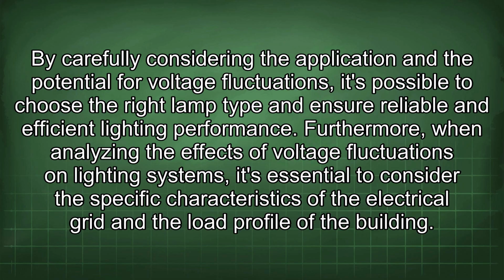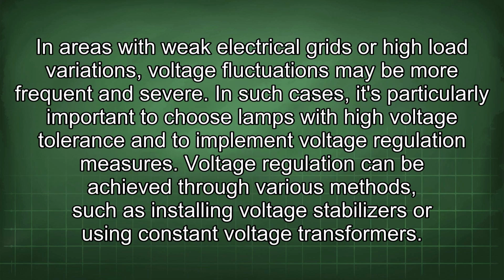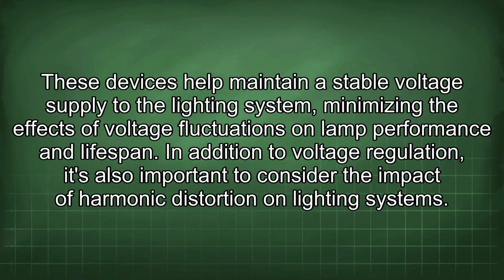Furthermore, when analyzing the effects of voltage fluctuations on lighting systems, it's essential to consider the specific characteristics of the electrical grid and the load profile of the building. In areas with weak electrical grids or high load variations, voltage fluctuations may be more frequent and severe. In such cases, it's particularly important to choose lamps with high voltage tolerance and to implement voltage regulation measures. Voltage regulation can be achieved through various methods, such as installing voltage stabilizers or using constant voltage transformers.